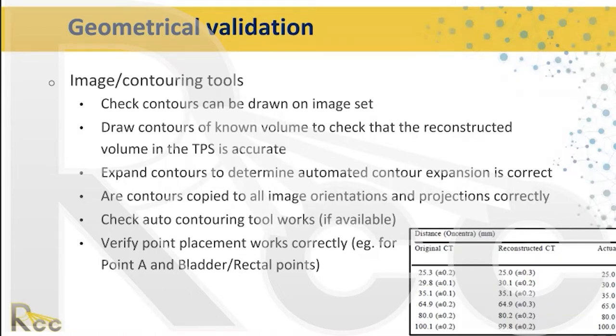We verify that the projection of a contour on a specific image orientation makes sense in all other orientations — for example, a contour in the axial slice should appear correctly in the coronal and sagittal views with the right shape and volume. Any auto-contouring tools available should also be verified. It is also important to verify point placement — for GYN brachytherapy, correctly localizing point A, point B, and rectal and bladder points.